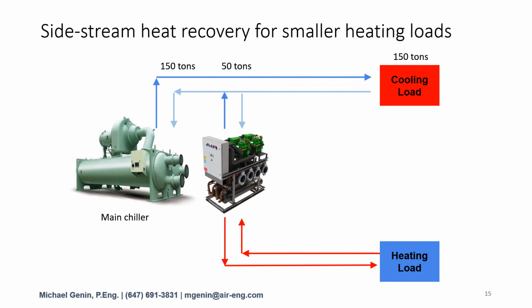We've chosen to pipe this chiller in a side stream configuration upstream of the main large chiller. The return chilled water pipe will be pre-cooled by the heat recovery chiller. This makes sense if your heat recovery chiller is small compared with the main chiller, or if you only have access to the return chilled water line. It's also an excellent choice for retrofit applications as well.